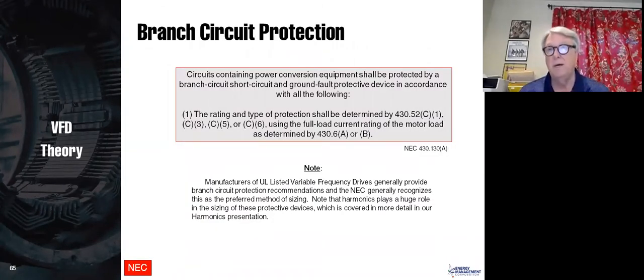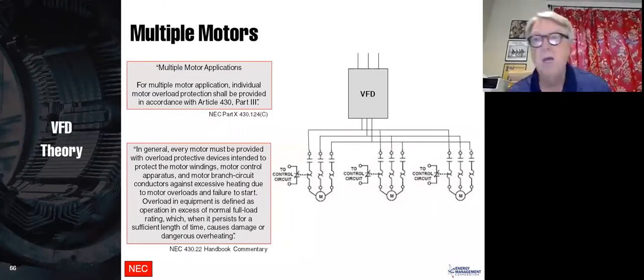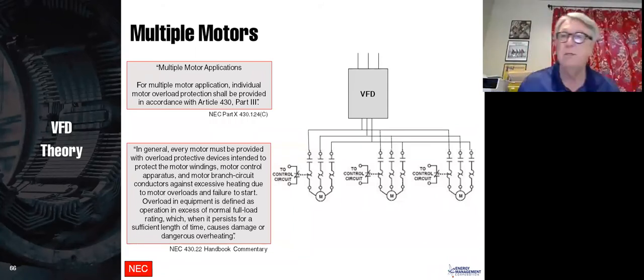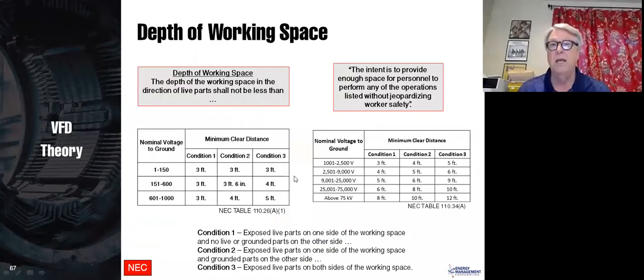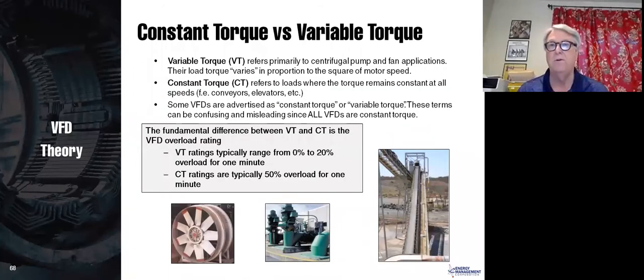This has some stuff on the code, and you can read that. Basically saying you've got to have branch short circuit protection, and it talks a little bit about that. A drive can run multiple motors. If you run multiple motors on a drive, then obviously the drive doesn't know how much current is going into each of the motors. Therefore, you have to have separate overload protection and typically separate contactors on each motor. But this is a very common application. Here's the NEC again, talks about the depth of working space. Typically, we need 3.5 feet in front of the drive.